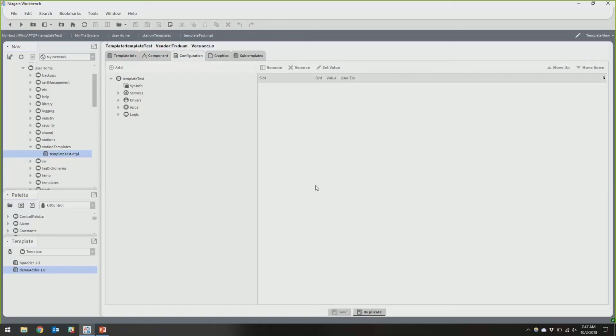For a job, you're going to use an 8000, and it doesn't expire, so you don't have to worry about that. But if you use your 8000 demo JACE, which obviously expires March 31st every year, the license will keep running, and the JACE will keep running until it restarts with an expired license. Most people don't realize come April 1st that their building JACE or their demo JACE doesn't work anymore. It's that power cycle where you catch it. It could be a month later, it could be a week later. It's just waiting, and then I get that frantic phone call or email that they can't get in.